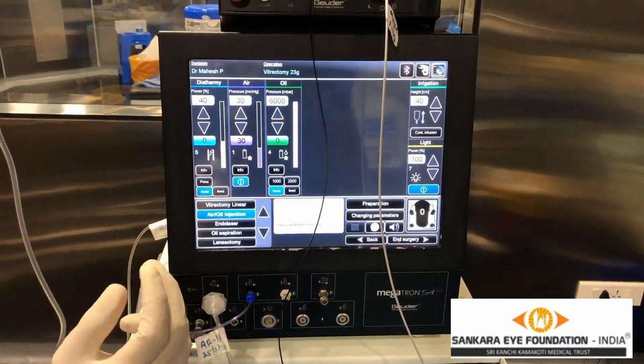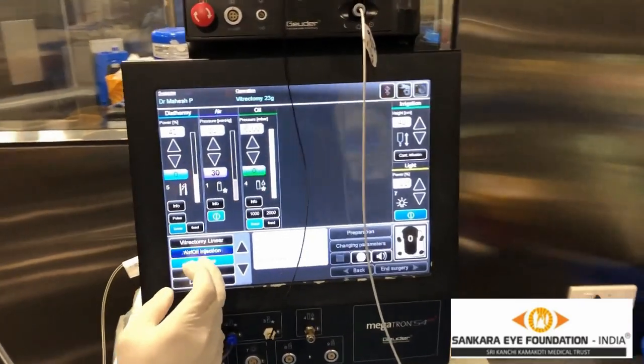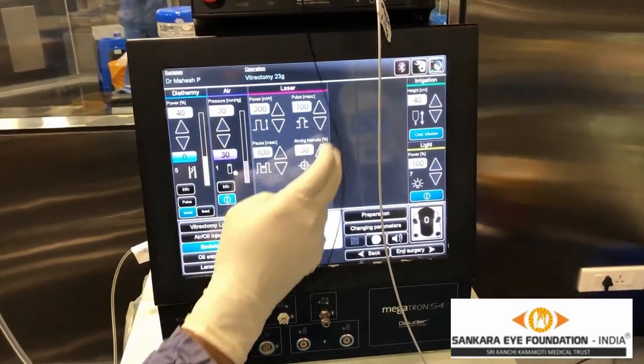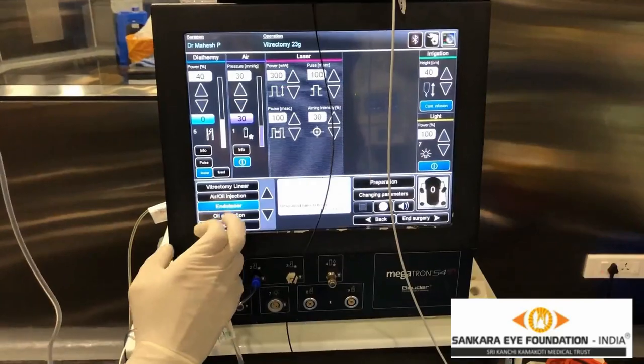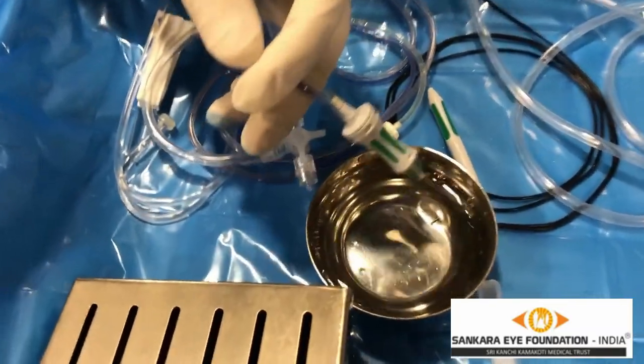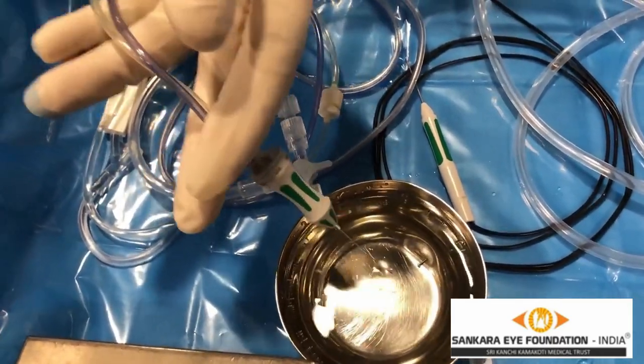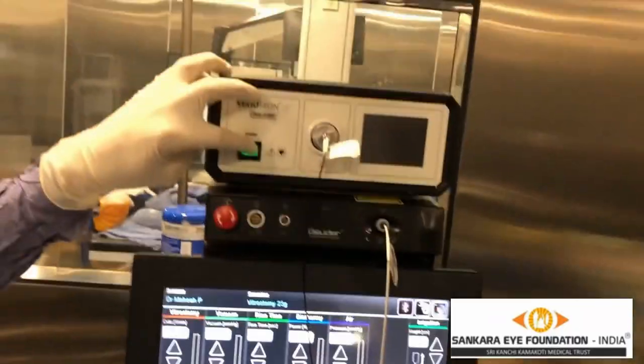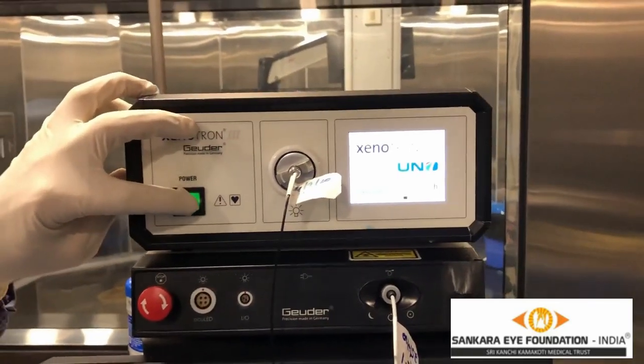This is for oil injection mode. As you can see, the oil injection mode is utilized and the air is also there. This is the laser mode where the laser machine parameters are shown — power, duration, and interval. There is an oil aspiration mode also. We check the cutter to confirm it is functioning correctly, whether the air is coming through and whether it is cutting. The light probe is connected to the light source and we verify the light is coming through.